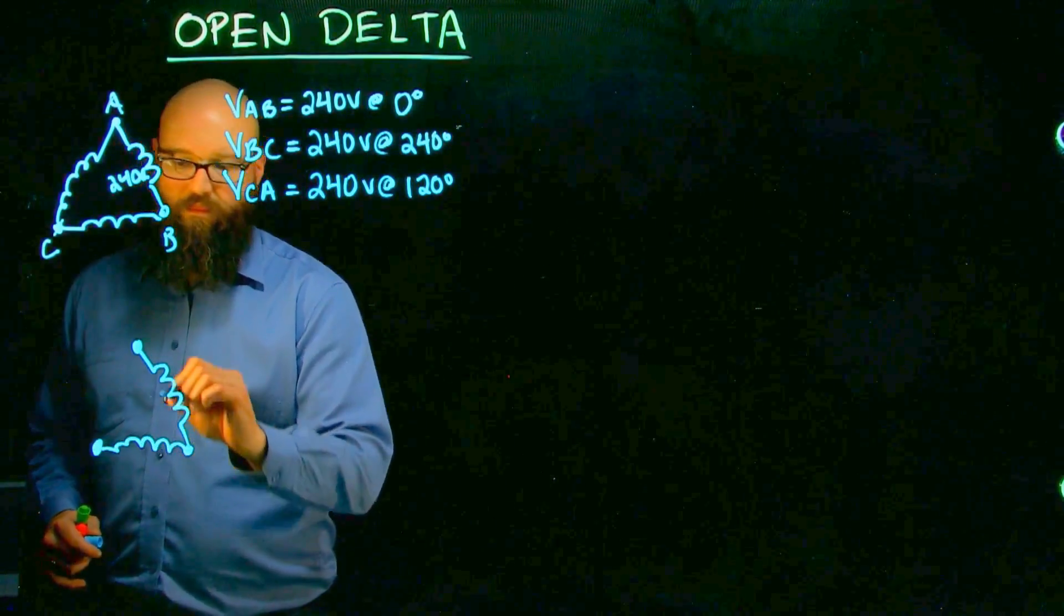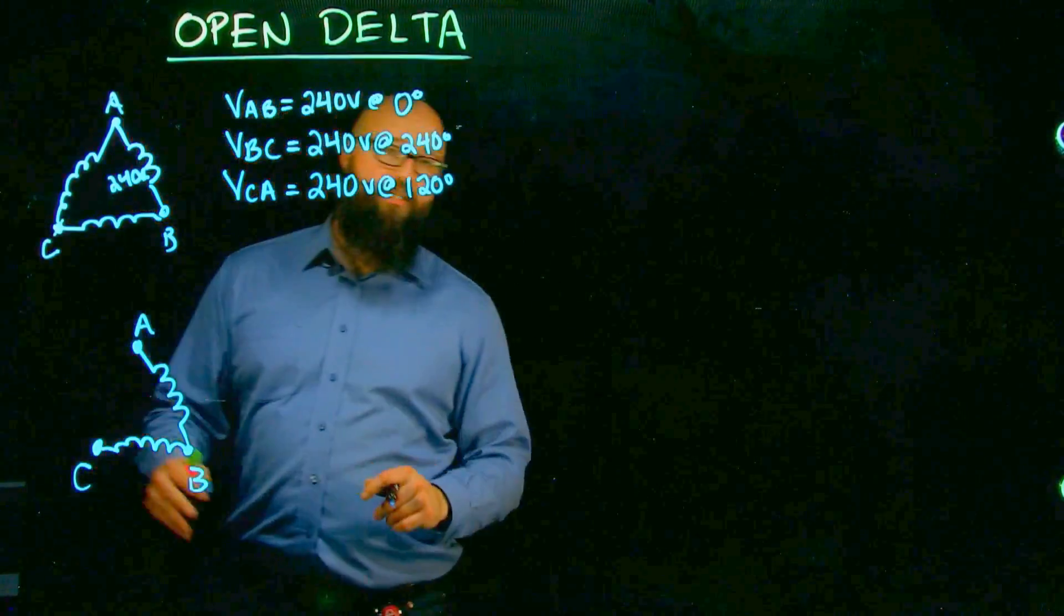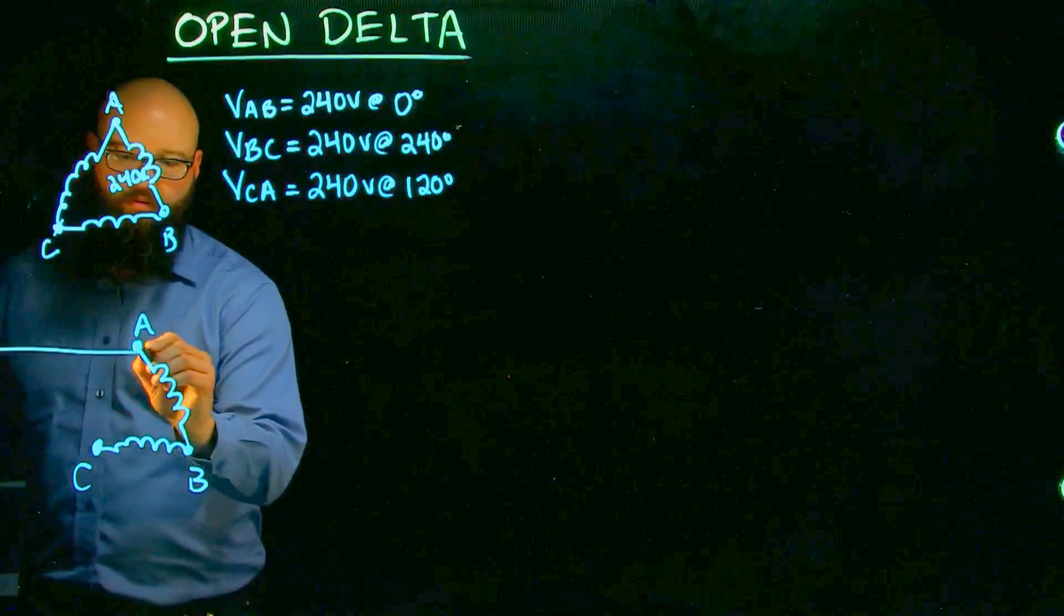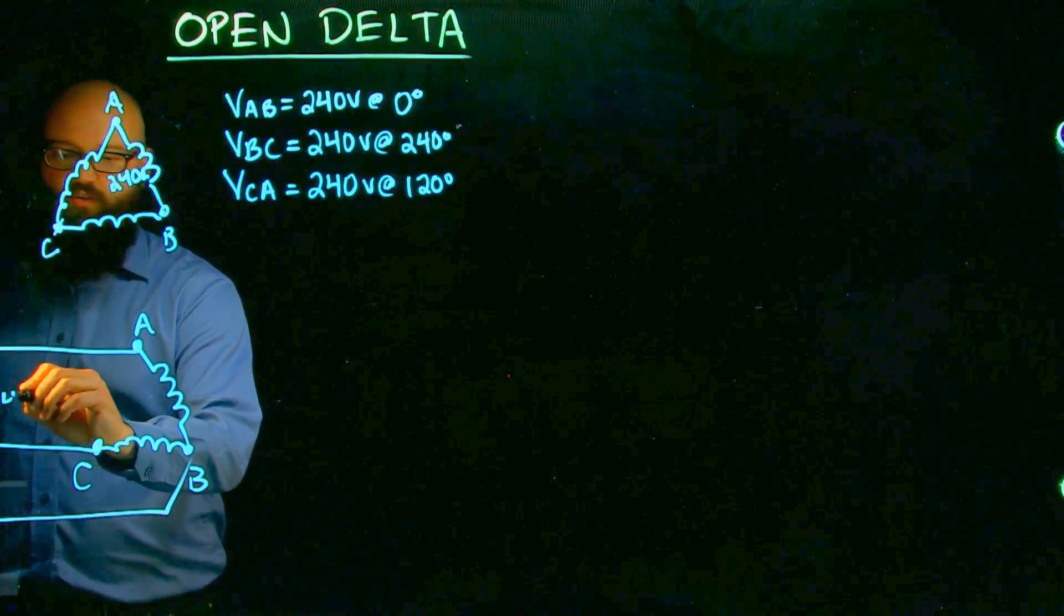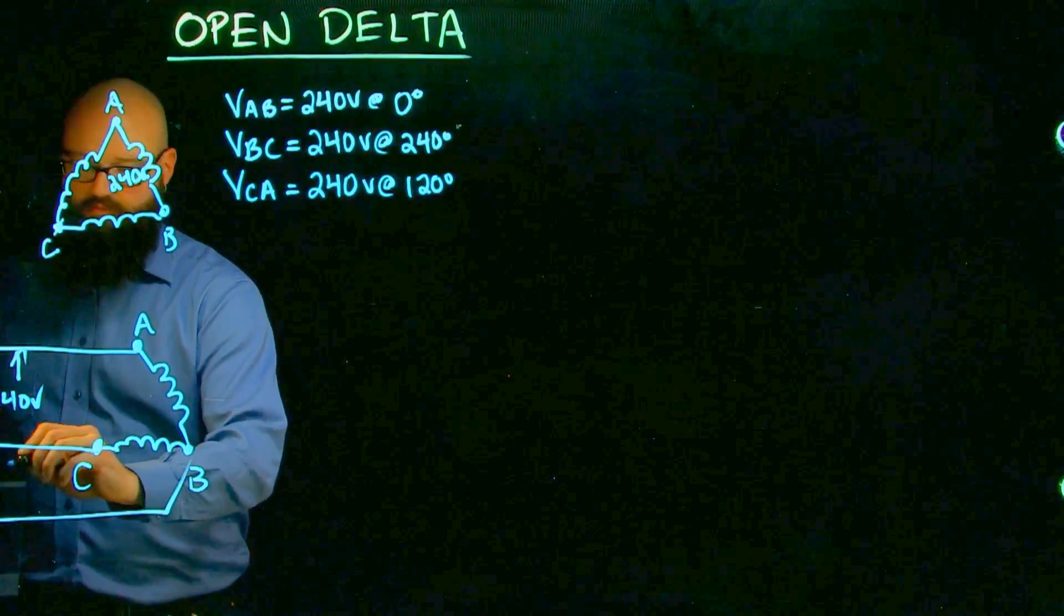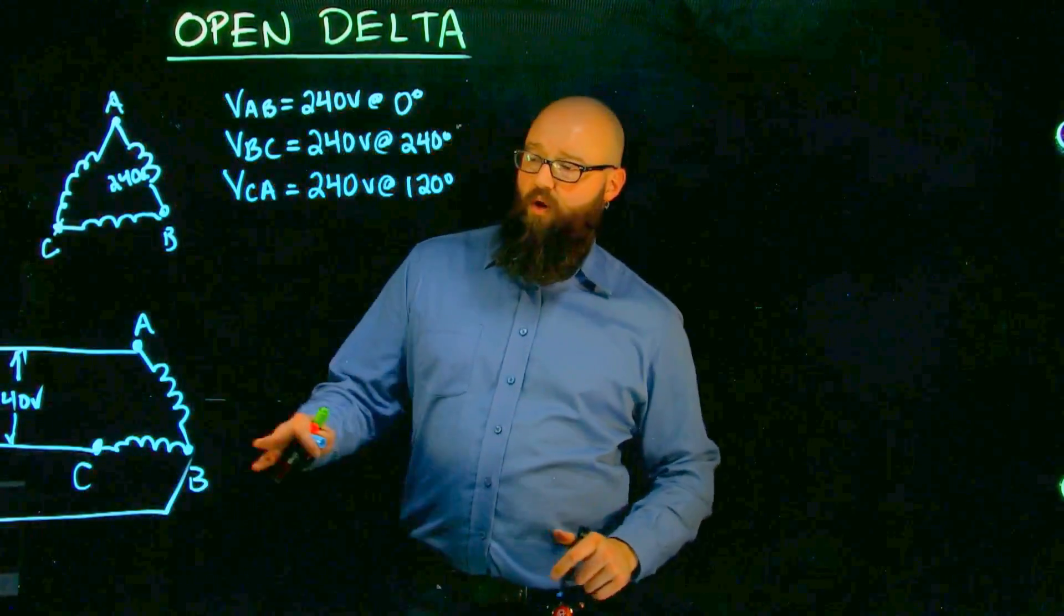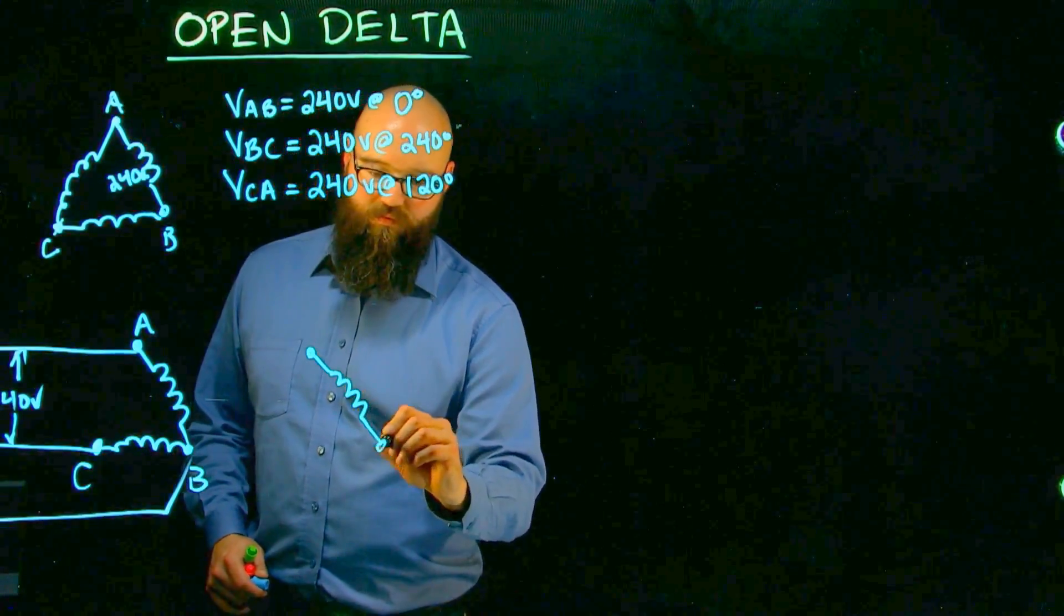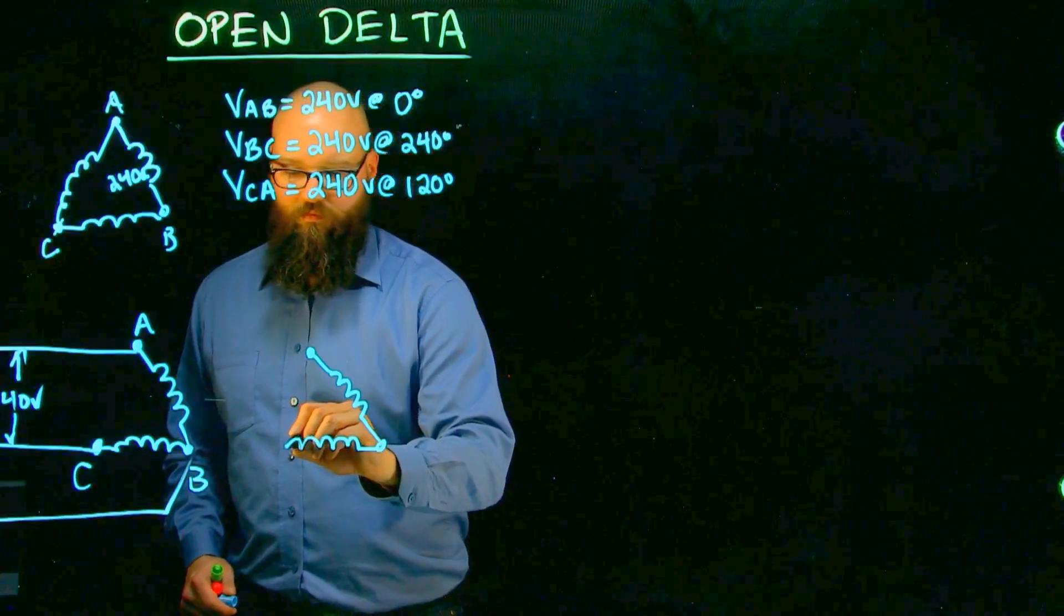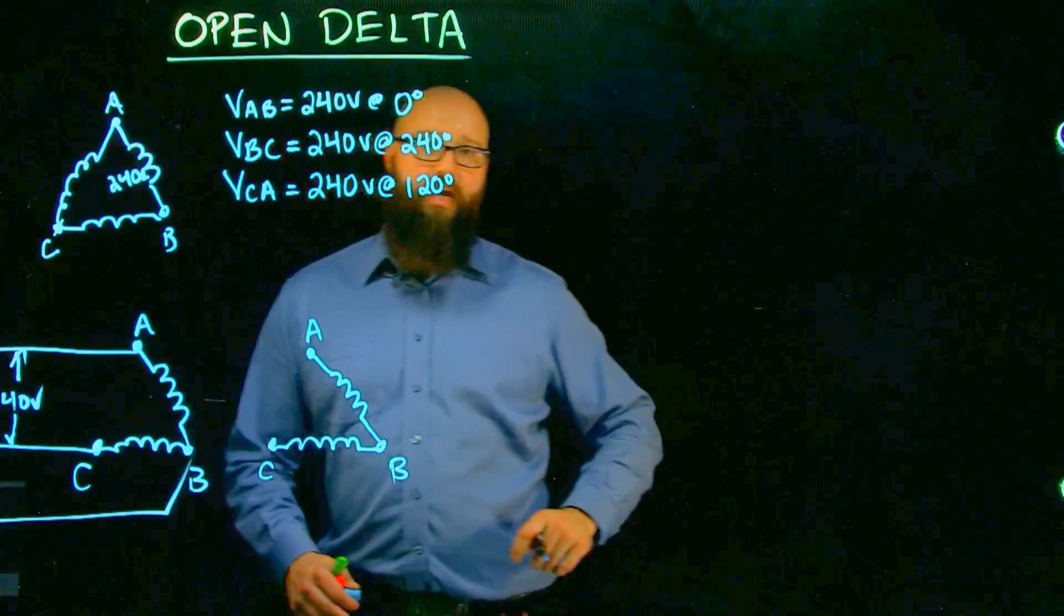So let's look at what happens with an open delta. A, B, C. We still have our applied voltage from our source of 240 volts line to line. When we lose that winding, we still have A, B, C.